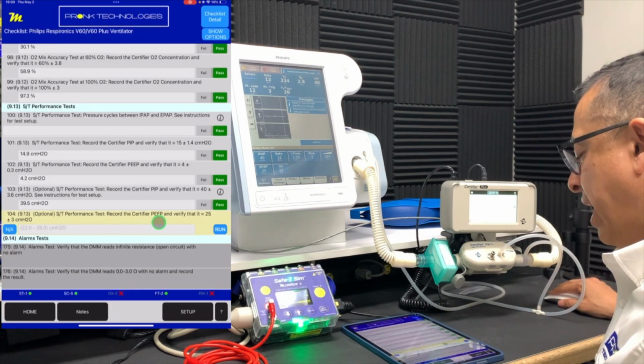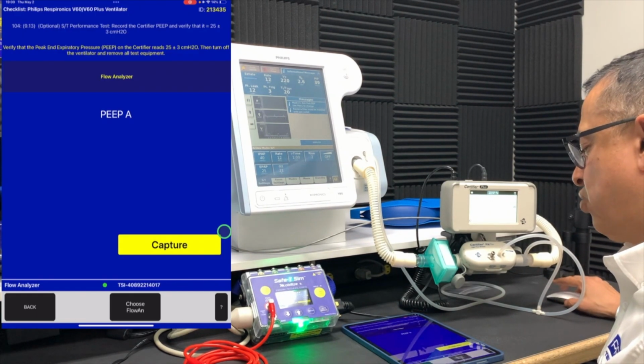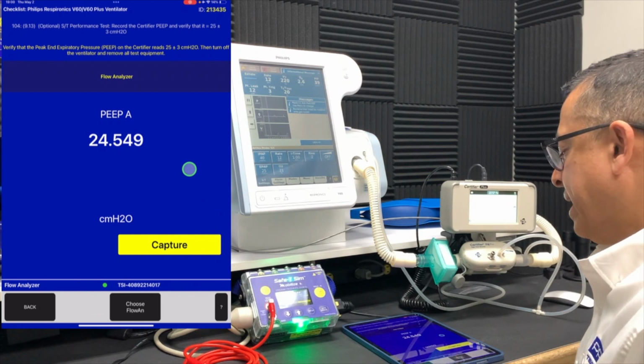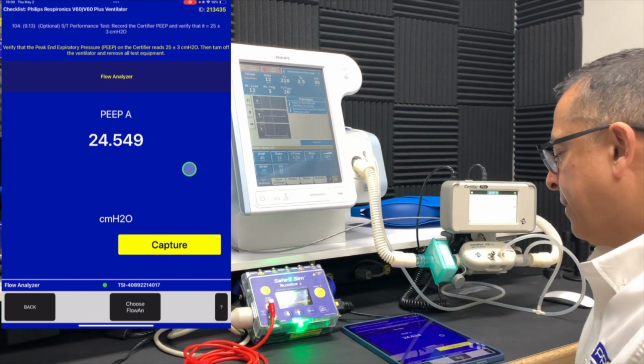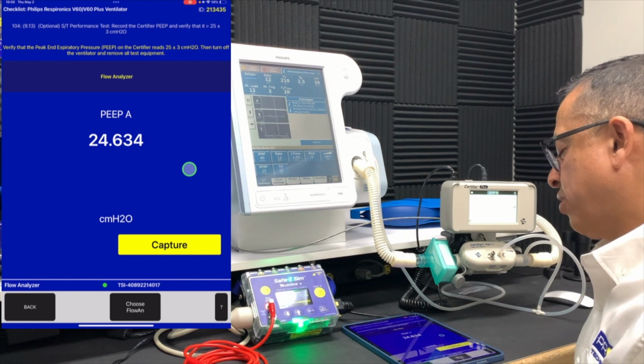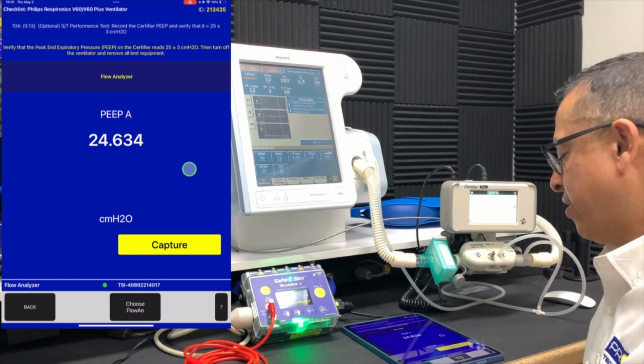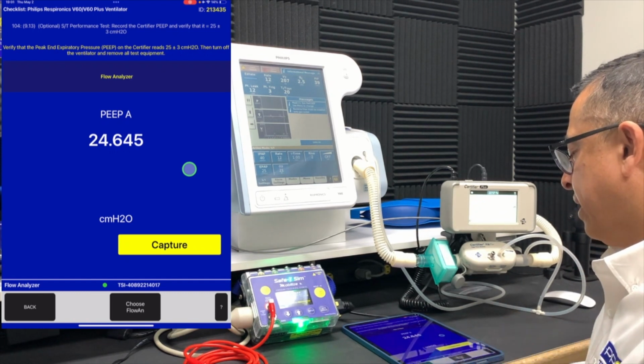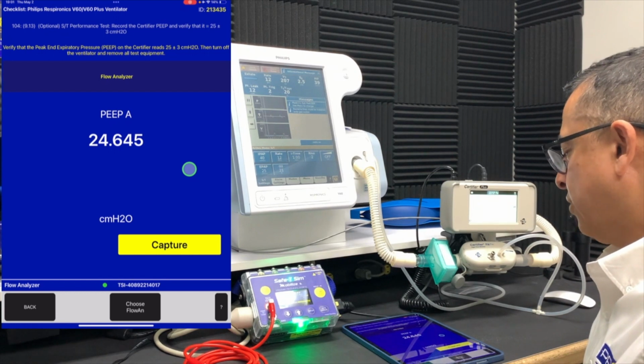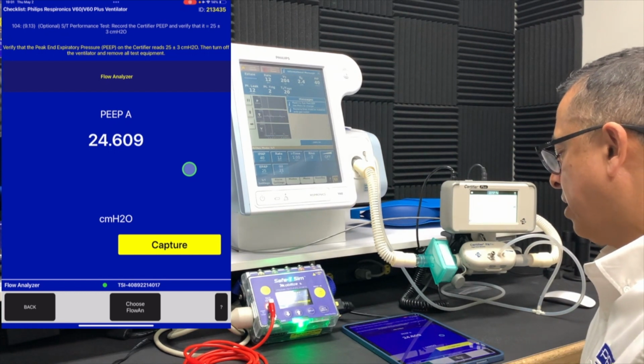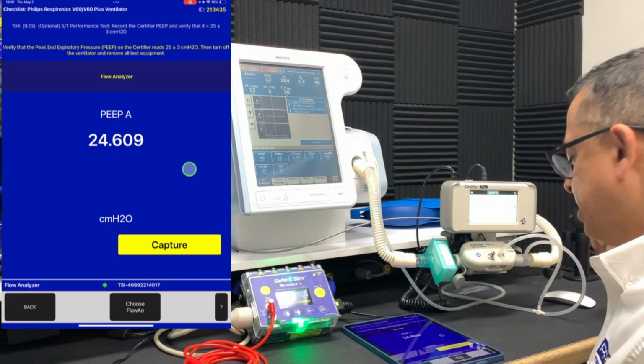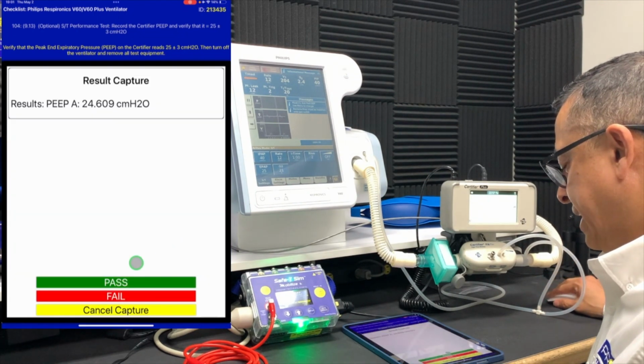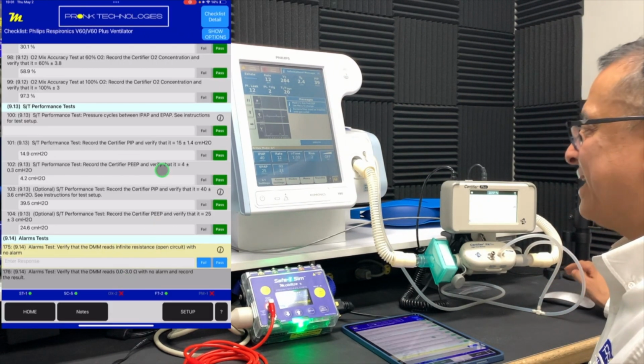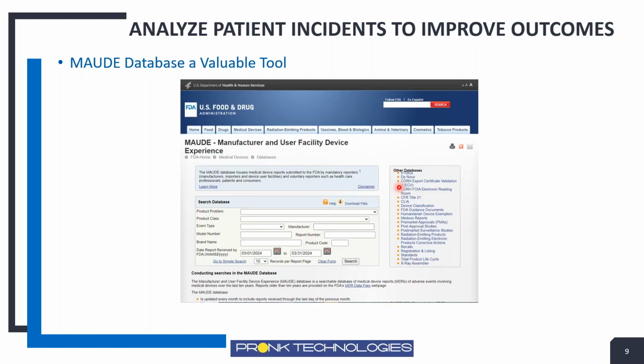Now we want to verify our PEEP as well is at 25 plus or minus 3 to make sure that peak end expiratory pressure is within that tolerance. And we can see here that it's been running for quite a while now, and it's holding within tolerance. We'll monitor it a little bit longer just to be sure, but we can see here that PEEP value is within tolerance, and that value does pass. So we finished that test.